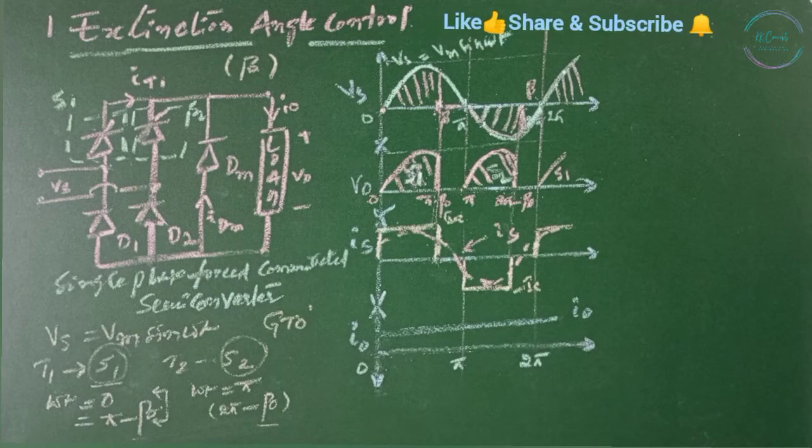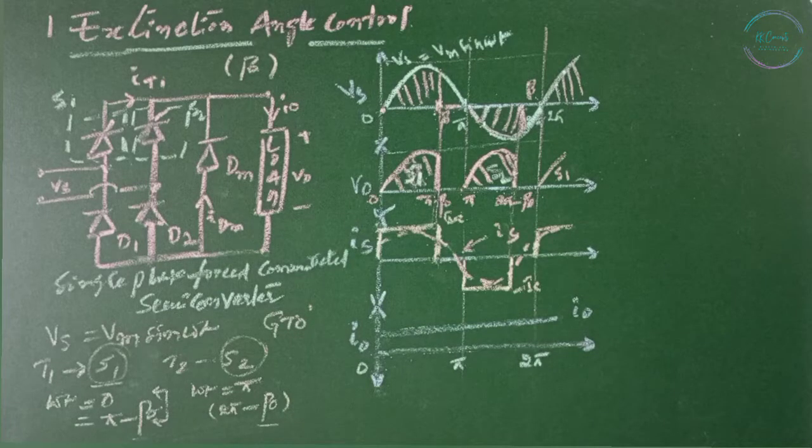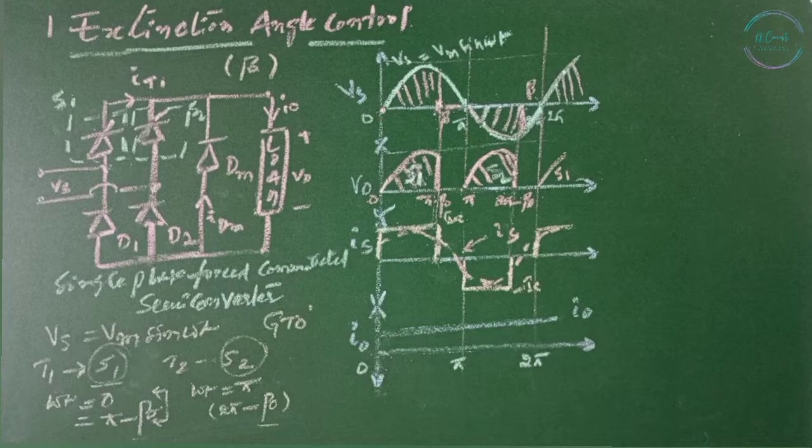You can see the fundamental current is going to lead. The fundamental input current leads the input voltage and the displacement factor is leading. Displacement factor is nothing but the power factor. In some applications, this condition may be desirable to simulate a capacitive load and to compensate for line voltage drops.